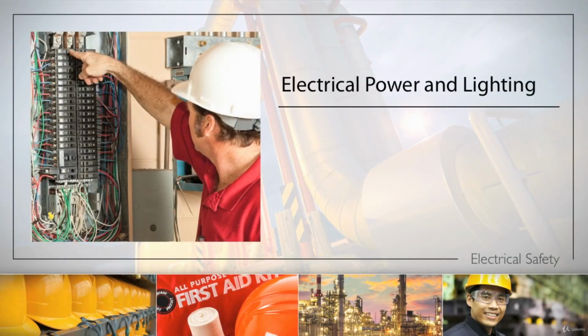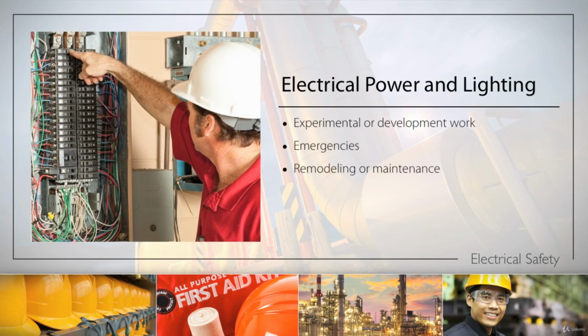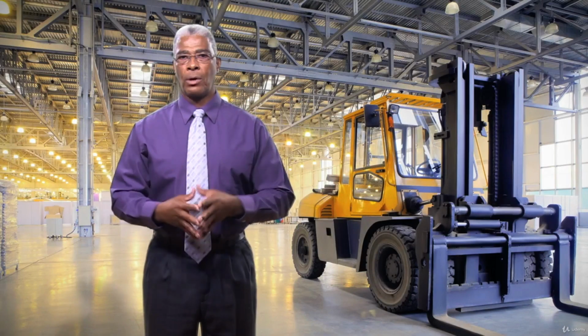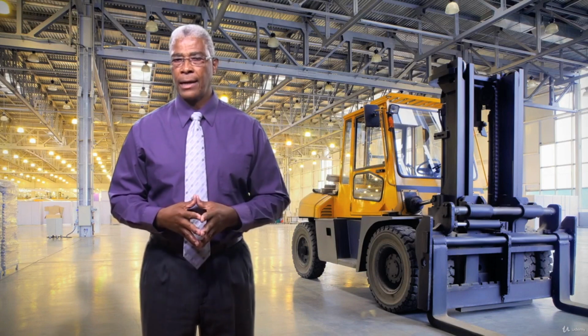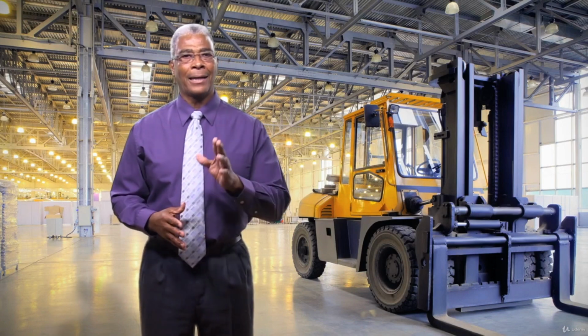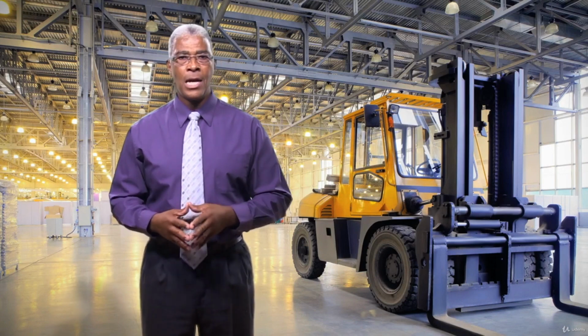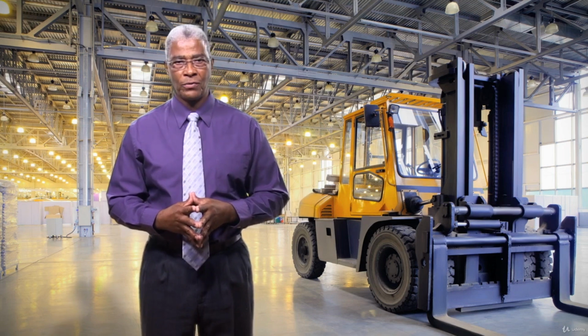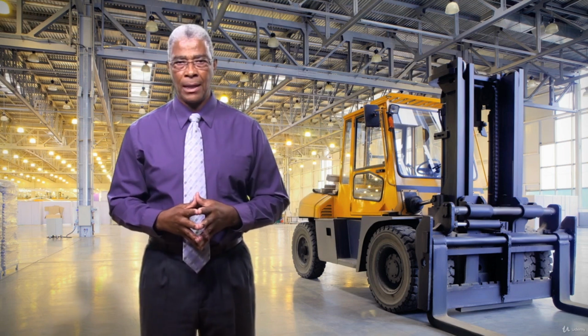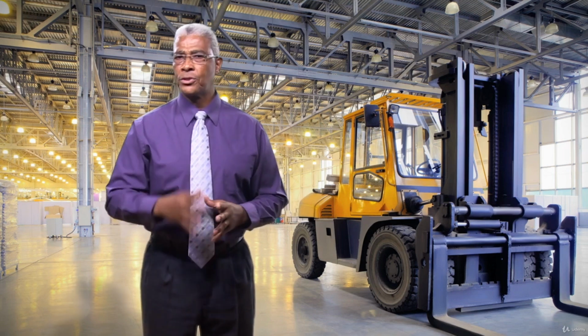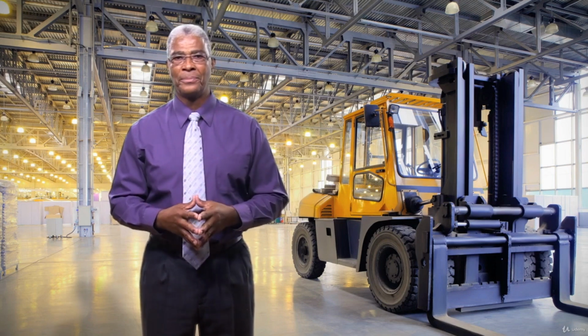Temporary electrical power and lighting installations of 600 volts or less may be used only for experimental or development work, during emergencies, for remodeling or maintenance, and for repair of buildings, structures, or equipment, and similar activities. If temporary wiring is used for the purpose of Christmas decorative lighting, carnivals, or other similar purposes, it cannot be installed for longer than 90 days. Once the purpose for which the temporary wiring was installed is fulfilled, the wiring must be removed immediately. If it is not removed, this could constitute a serious electrical violation.